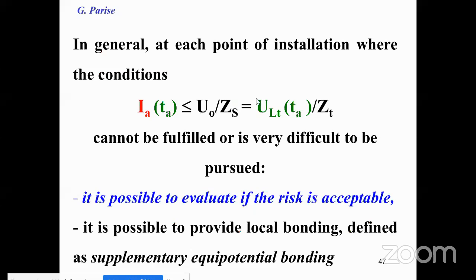Okay, we have discussed the general requirement, but when it's not possible to respect the condition, how is it possible to operate? It's possible to evaluate if the risk is acceptable. If yes, it can be permitted, even if the condition is not satisfied. Otherwise, it is always possible to provide local bonding, defined as supplementary equipotential bonding.